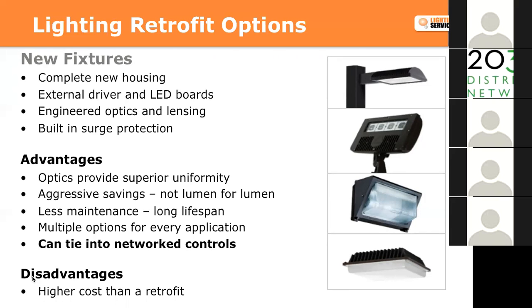As you can see some of the advantages here, I'd say there's three important things. One would be optics - actually getting the light where you need it, not just for energy efficiency, but for safety. Also lifespan - these things last, say, 100,000 hours or more, whereas the corncob style or any real retrofit product has roughly half the life at best, typically. The other reason these are nice is you can tie them into network controls. Those are probably the most important reasons, although there are others, and the efficiency of these fixtures is significantly higher, so the energy savings is better as well.